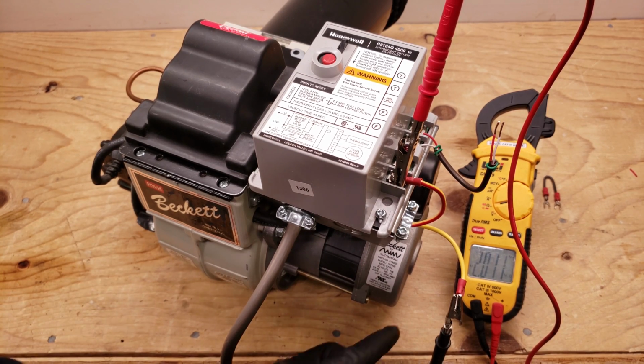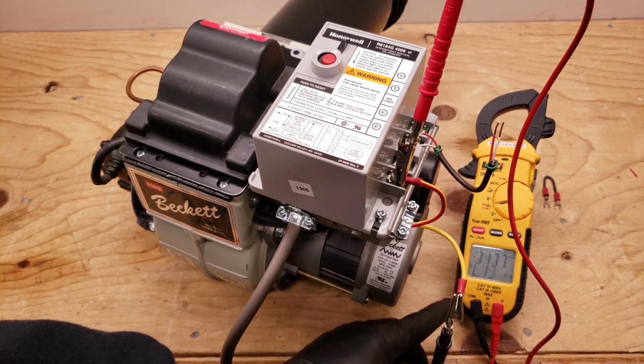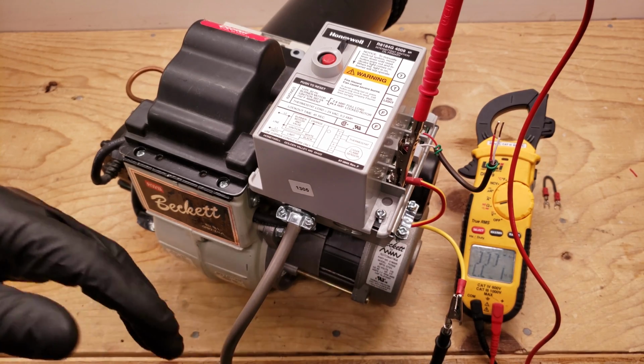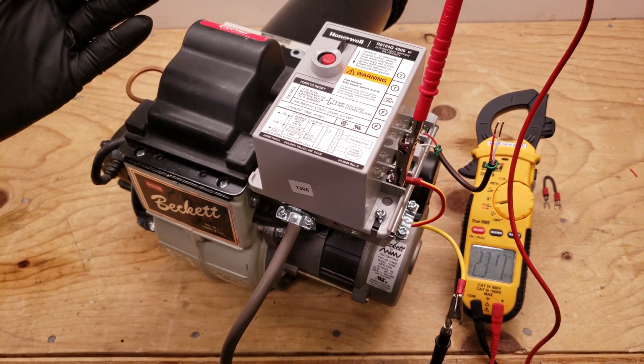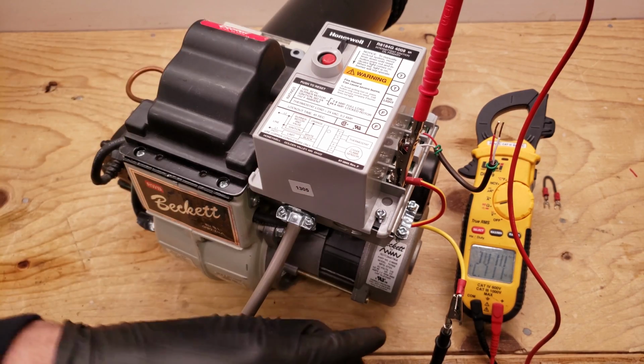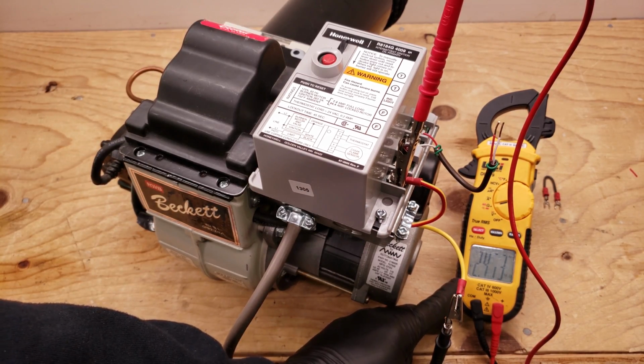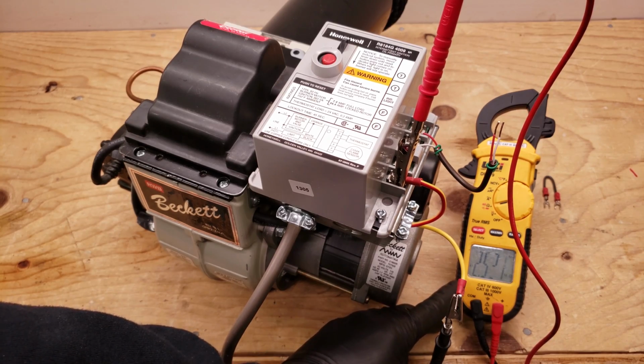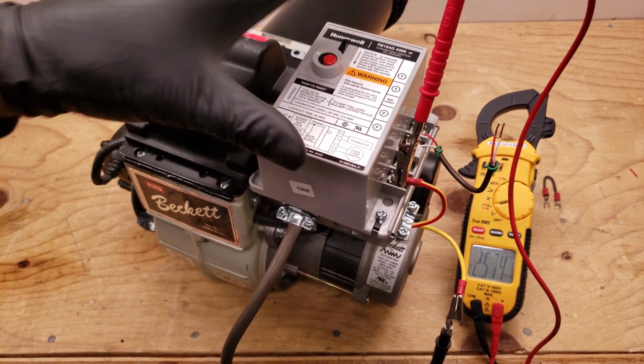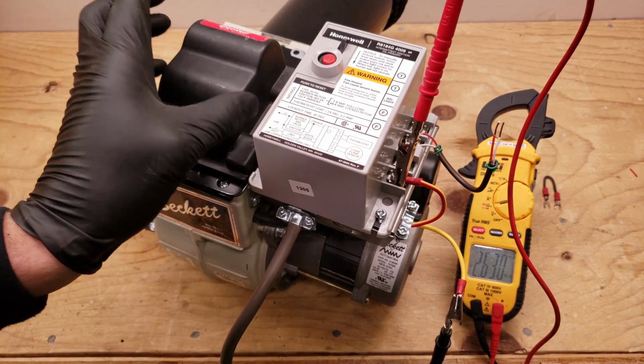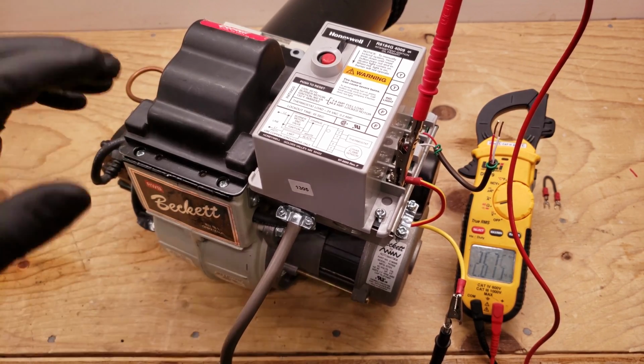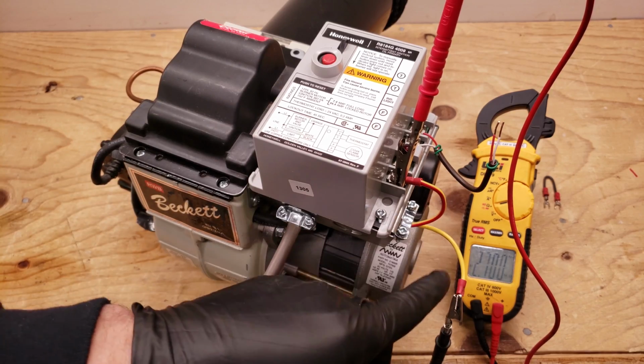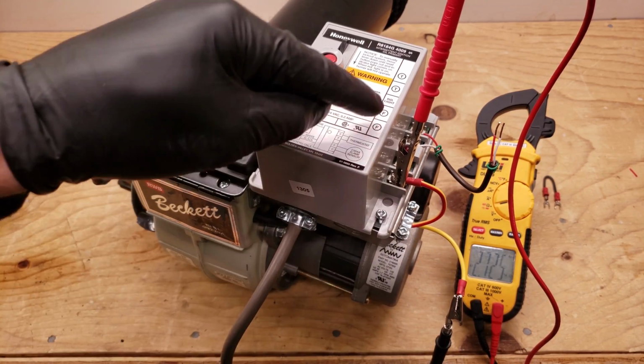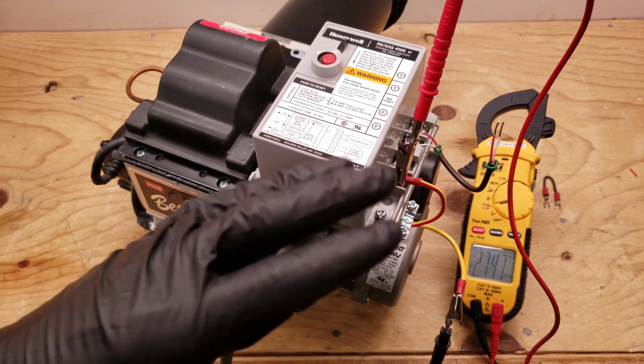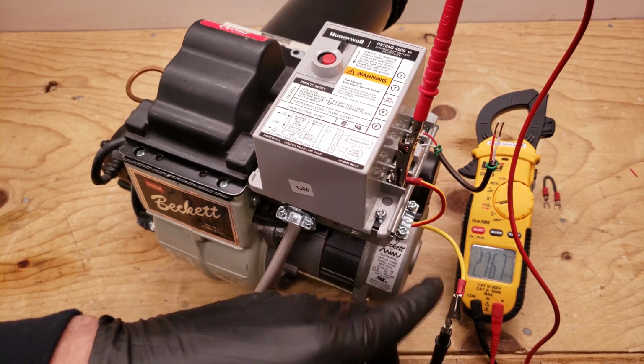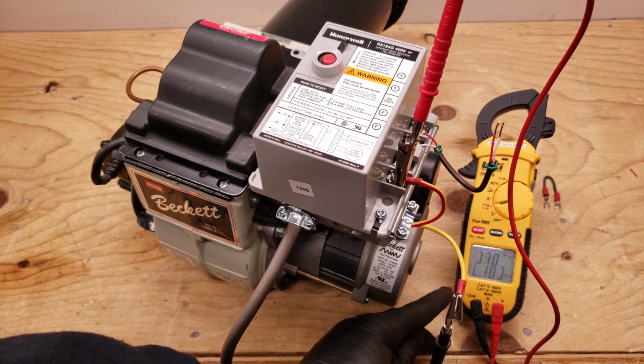So right now you see that I'm in megaohms. It says 2.1 megaohms of resistance. So right now you should have some type of megaohm resistance. And if you had anything right about 1600 ohms or lower, then this primary control is not going to send voltage to the motor, to the transformer, and to the solenoid. So it's not going to turn on if we have a resistance value on the F and the F terminals from the CAD cell of below 1600 ohms. Right now, obviously, we're disconnected, but that's a good reading.